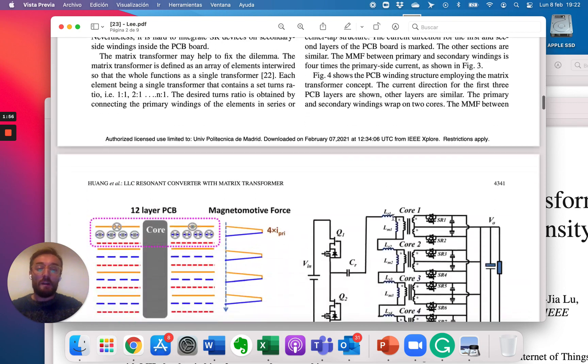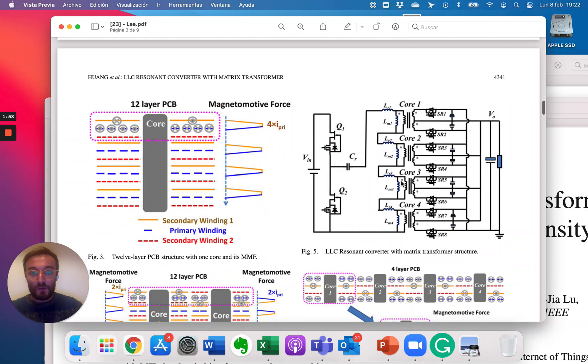Then they propose this structure where instead of one transformer with several outputs in parallel, they have four transformers with four primaries in series and four secondaries in parallel.